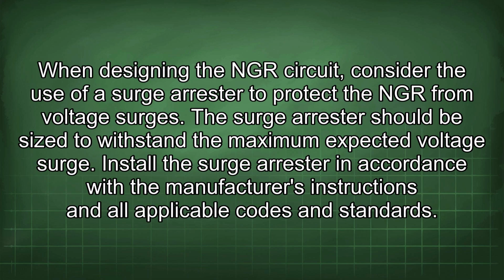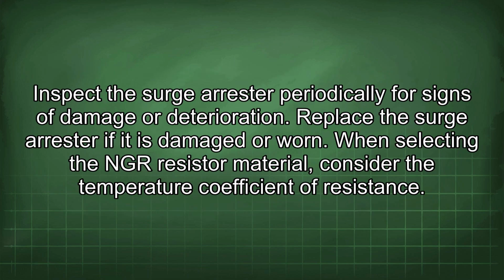When designing the NGR circuit, consider the use of a surge arrestor to protect the NGR from voltage surges. The surge arrestor should be sized to withstand the maximum expected voltage surge. Install the surge arrestor in accordance with the manufacturer's instructions and all applicable codes and standards. Inspect the surge arrestor periodically for signs of damage or deterioration. Replace the surge arrestor if it is damaged or worn.